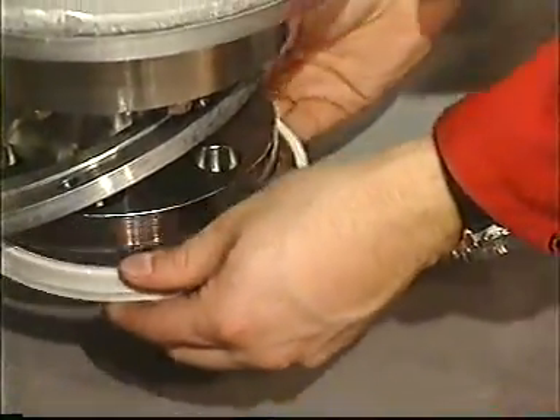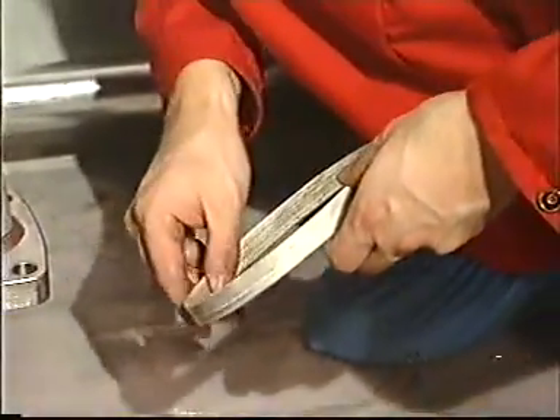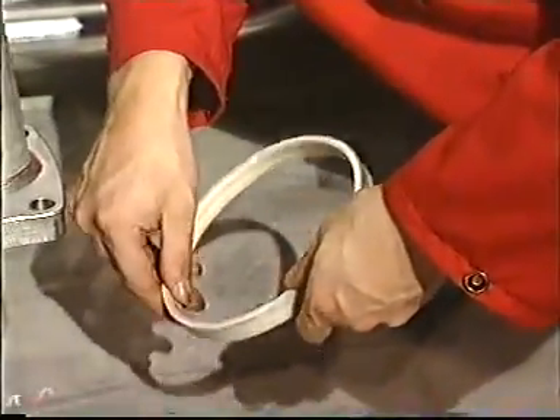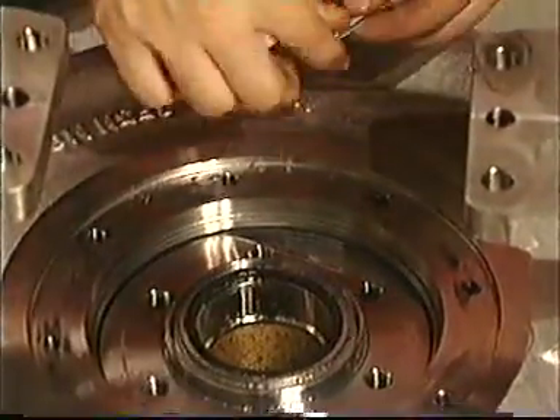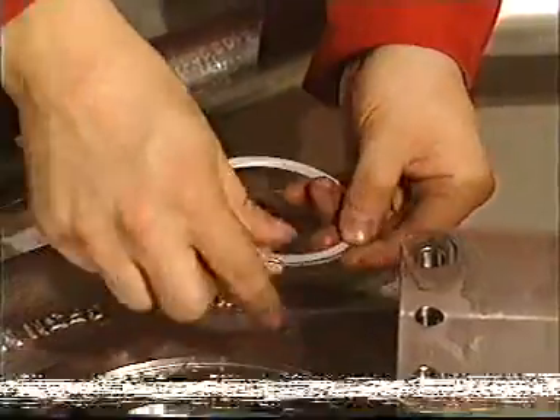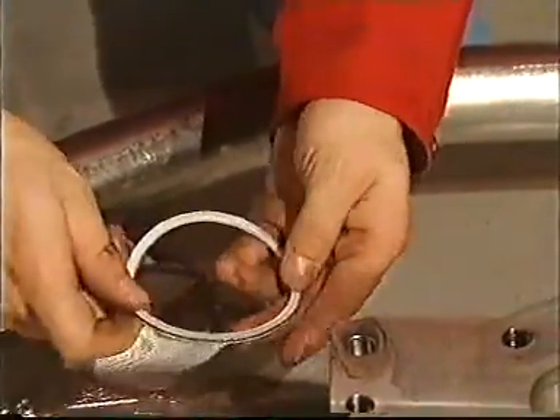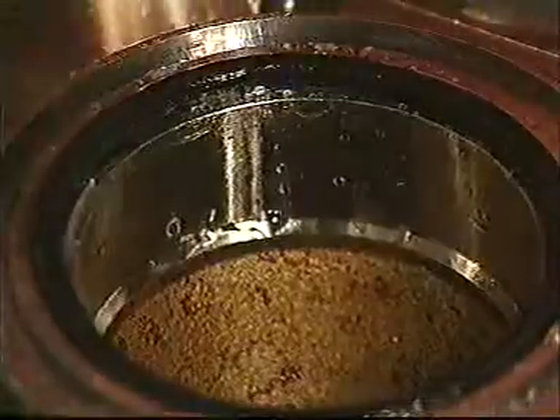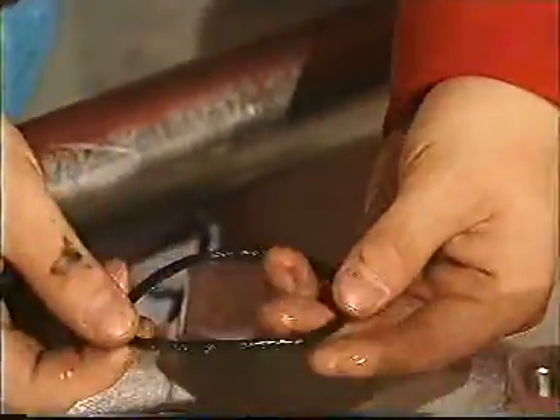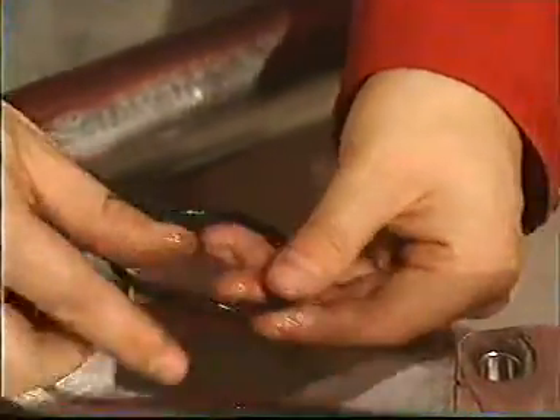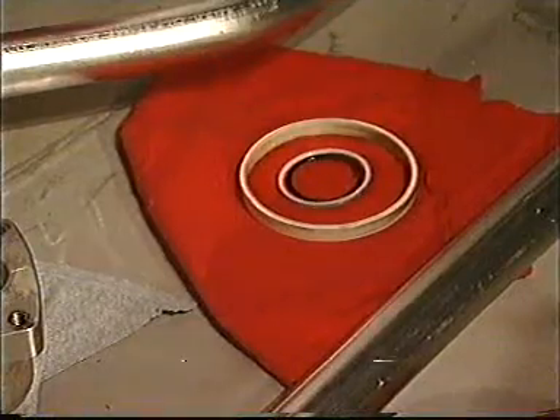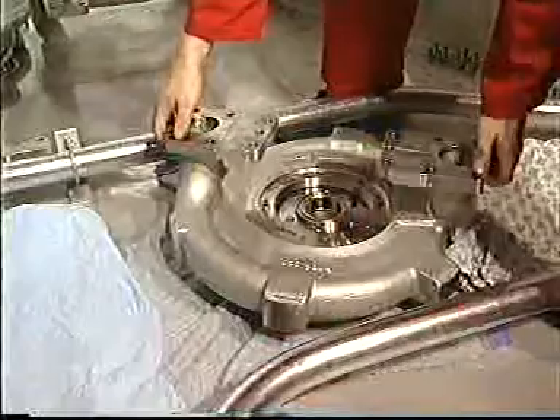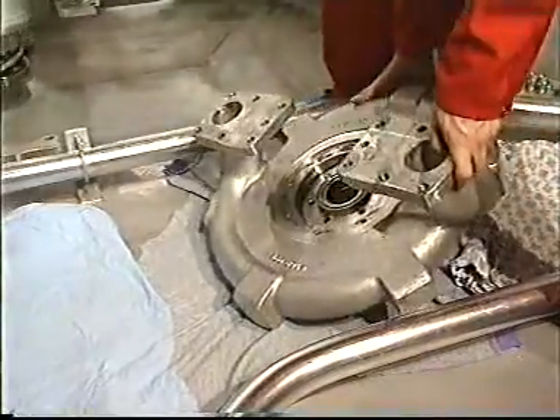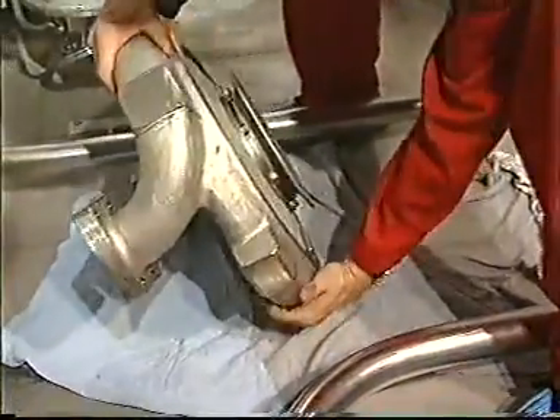Remove the upper wear ring and inspect it carefully. Remove the seal element and the O-ring between impeller and impeller hub. This is normally parts fit for further use, but have to be controlled and clean before assembling. The next step is to turn the unit upside down.